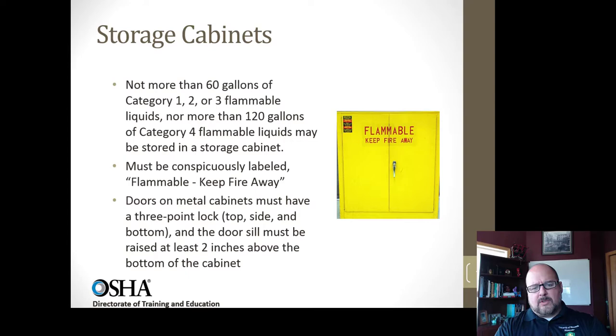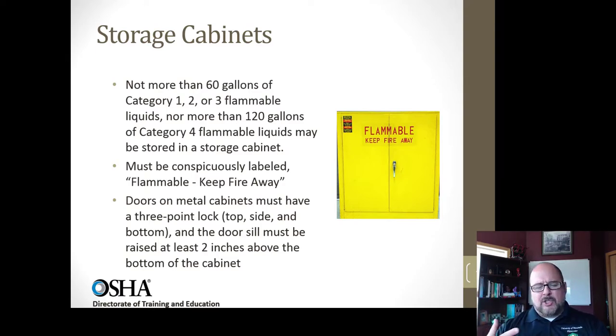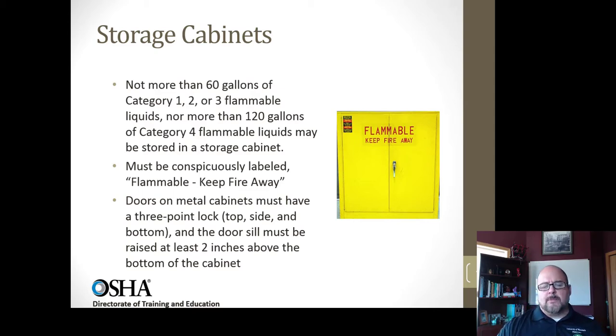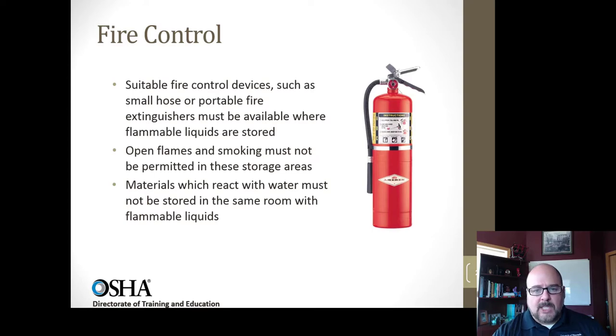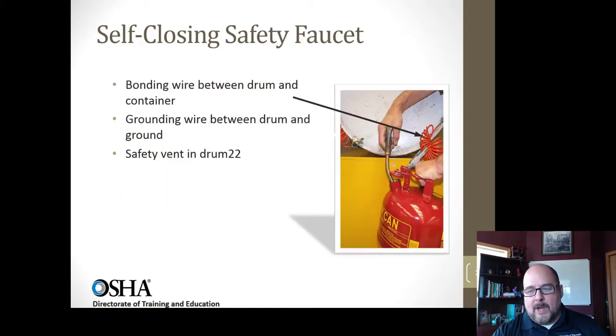Storage cabinets have many requirements under OSHA 1910-106. You can't really build your own — they must meet the standard. Shelves should be set up so that if a leak occurs, liquid runs backward and down and collects at the base. Cabinet doors should be self-closing and should never be left open; if they do need to stay open, a fusible link allows them to close automatically when heat is detected. Fire extinguishers and a fire suppression system should be located nearby, and when transferring, make sure it's a closed loop.